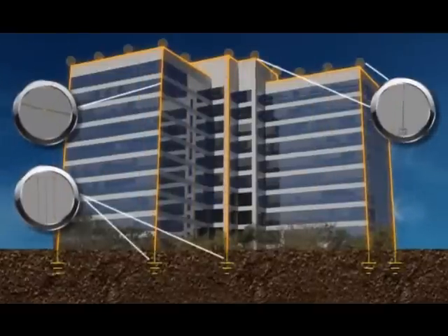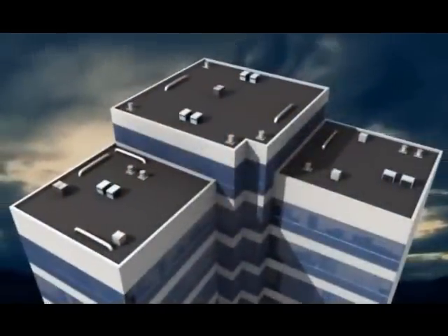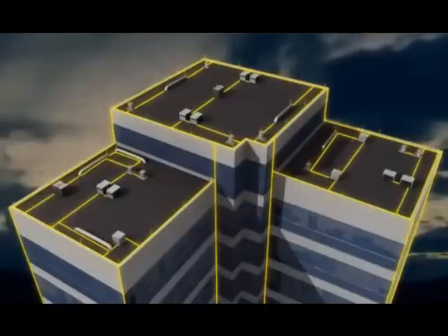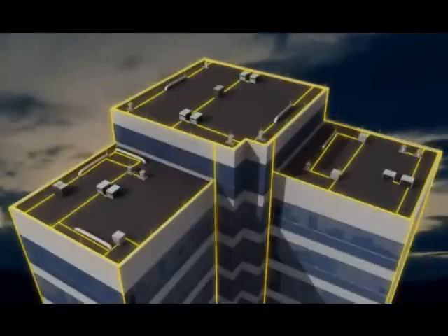On a flat roof structure, this interconnected system is also routed through the mid-roof areas and bonded to the required rooftop mechanical equipment such as air conditioning units, exhaust fans, plumbing vents, roof drains, and roof ladders.